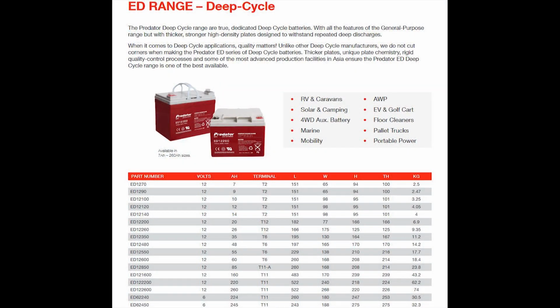So the batteries we are currently using are these Predator batteries. They're 220 amp hours each. So we have 2 sets in parallel, so that gives us a total of 440 amp hours, and at 48 volts that gives us 21,120 watt hours, or 21 kilowatt hours of storage at 100% capacity. But you should never use that much out of a lead acid. So at 50% capacity, that would give you 10.56 kilowatt hours of storage, and we only ever use a maximum of 30% out of the batteries. So at that we would have 6.336 kilowatt hours, or 6,336 watt hours of storage in our battery bank if we only draw out 30%.